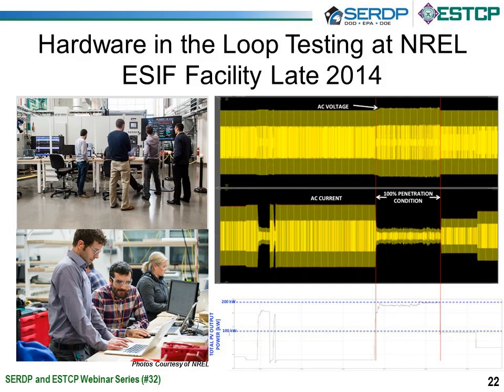This gave us a lot of experience. We were able to hash through a lot of the controls on the power electronics side and the DC controls of the battery. A lot of those things are important to maintain proper power quality output for the load conditions. When AC systems kick on, you get big load steps. The other thing we wanted to make sure of was the stability of the system, because we're an all-renewable-based microgrid. There are no inertial sources on this. We have PV inverters and a battery inverter providing our generation assets. When we start integrating those together and ramping up the PV and sharing that power generation with the battery, we wanted to make sure we don't run into the controls on each element fighting against each other. We wanted to maximize the amount of PV we utilize, so the battery output is minimal and just provides a voltage regulation source.